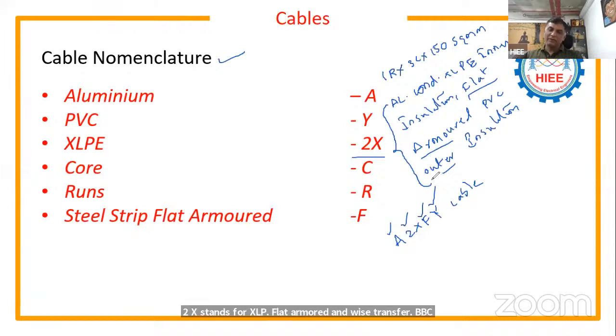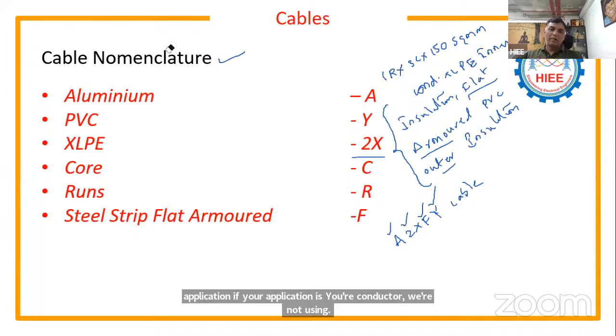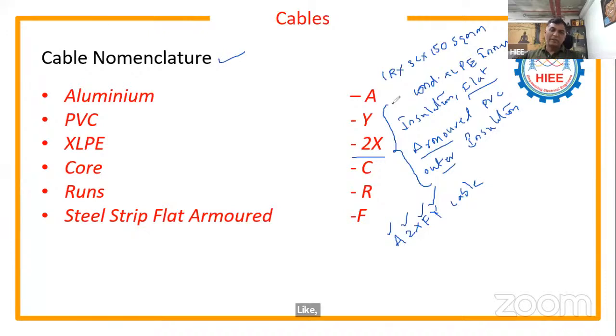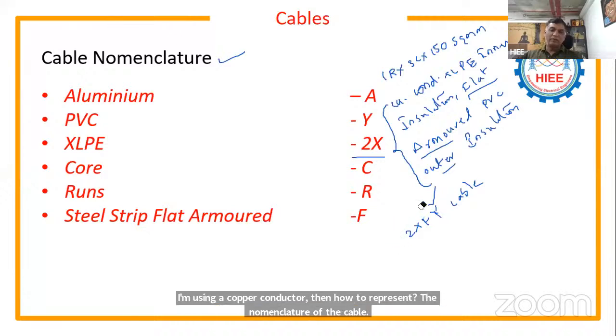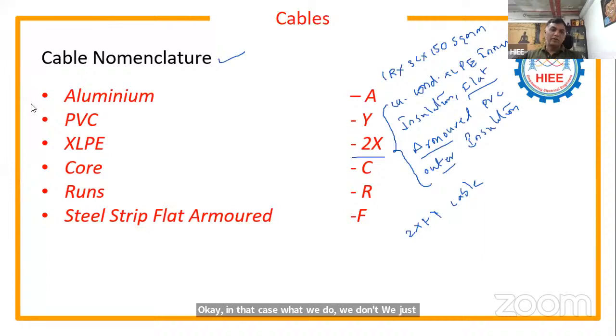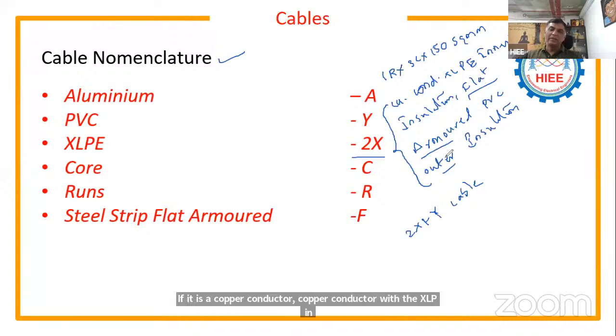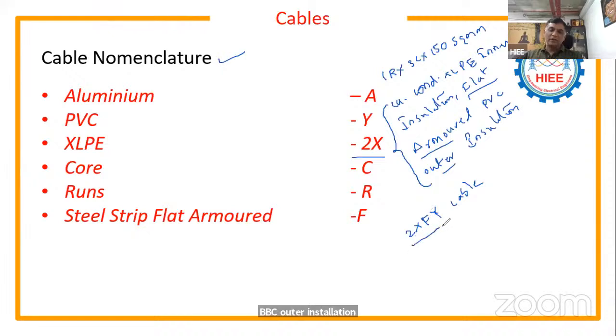Okay, so for example, if in your application we are not using an aluminum conductor, I'm just using a copper conductor, then how to represent the nomenclature of the cable? In that case, we just remove A. A copper conductor with XLPE inner insulation, armored, with PVC outer insulation is defined as the 2X FY cable. If A is there, that is for aluminum. If A is not there, that cable is a copper cable.